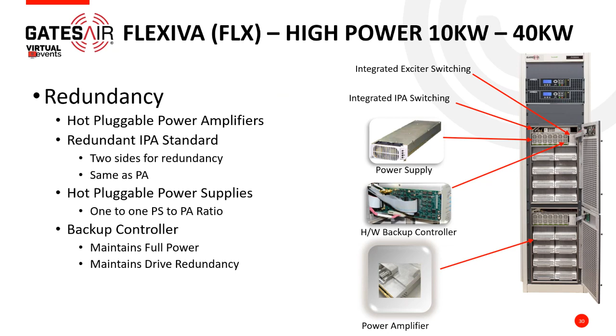Here's an exploded view. If I were to pull one of the modules—they are hot pluggable—you can see up into the PA itself. Within that, it has self-sealing fluid connections, so when you pull it out, nothing goes squirting anywhere. It self-seals, and you have a drip plate—you might have to clean it off, but that's it.